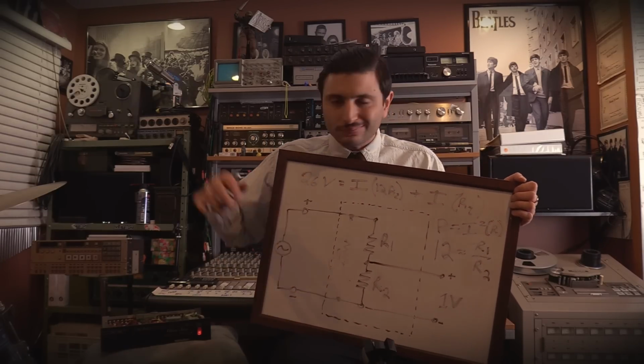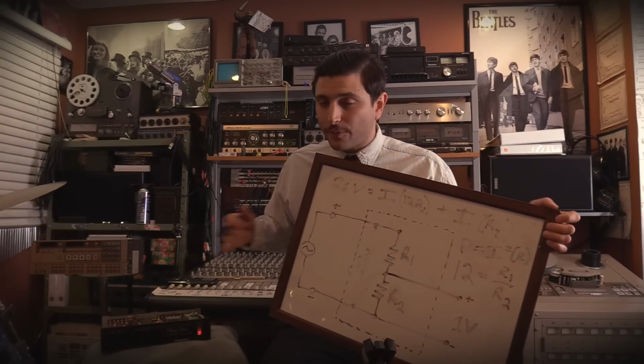Honestly, the tests I did that we're going to talk about right now, it hasn't been an issue, okay? Really the problem is whenever you introduce an output transformer and you don't have a load connected to that output transformer, you are going to cause voltage spikes on the primary side of that output transformer. Whenever you have a voltage spike, you're potentially introducing excessive voltages to the components in the system.